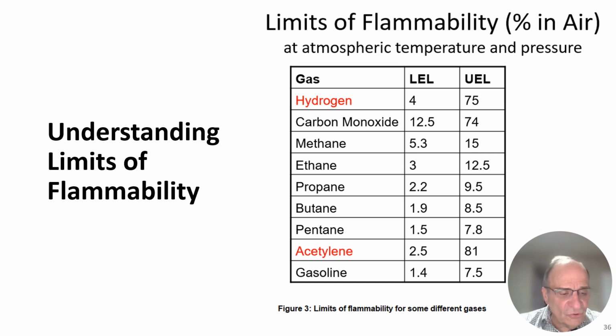And this was the table I was talking about earlier, and I mentioned hydrogen and acetylene as having a very wide flammability range. I didn't know the exact numbers, but I'm showing them here. Hydrogen is from 4% all the way up to 75%. So I can have 75% hydrogen in 25% air and have it ignite. Now, hydrogen is a fuel that you have to be very careful about, because hydrogen has a very low activation temperature, or very low energy level required to ignite it.